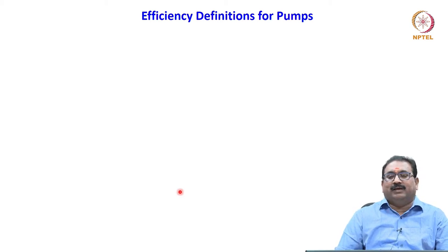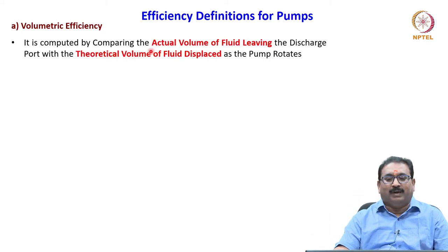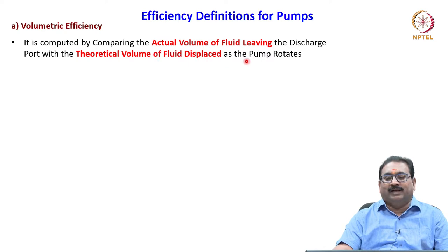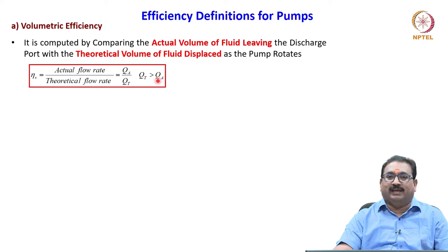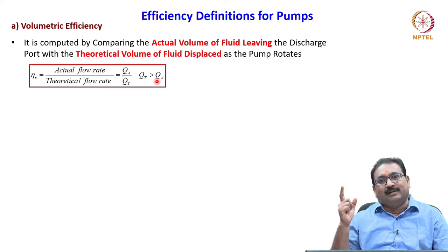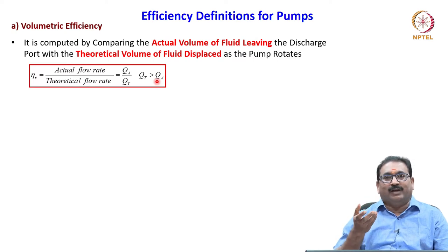Let us see the efficiencies of the pumps. The first one, as I told you, is volumetric efficiency, which accounts for leakage. It is computed by comparing the actual volume of fluid leaving the discharge port with the theoretical volume of fluid displaced as the pump rotates. Volumetric efficiency is the ratio of actual flow rate to theoretical flow rate — that is QA by QT. Always remember, the theoretical flow rate is greater than QA. Actual flow is always less because there is leakage between the rotating and the mating housing. If clearance increases, leakage is more and volumetric efficiency will be less.